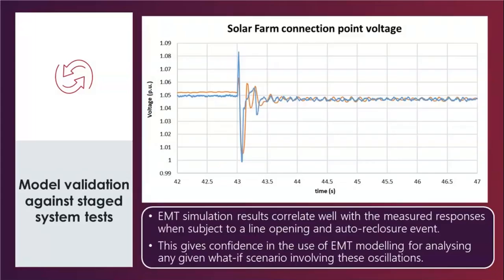To understand whether these oscillations are real or might simply be a modeling artifact, we conducted system level testing at different times. This example involved opening and switching a number of nearby transmission lines to vary the level of system strength available to those inverter-based resources. As we can see here, for one particular solar farm, the correlation between measured and simulated response is quite good. The simulated response, again, is based on detailed EMT modeling. This gives us confidence in the validity of our conclusions on how to plan and operate the power system for any given what-if scenarios.